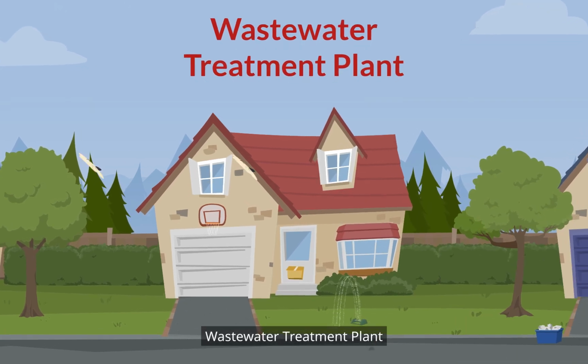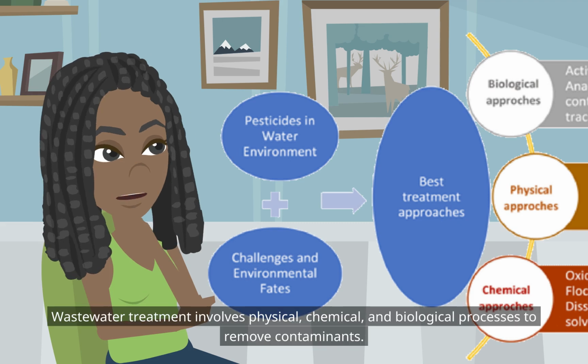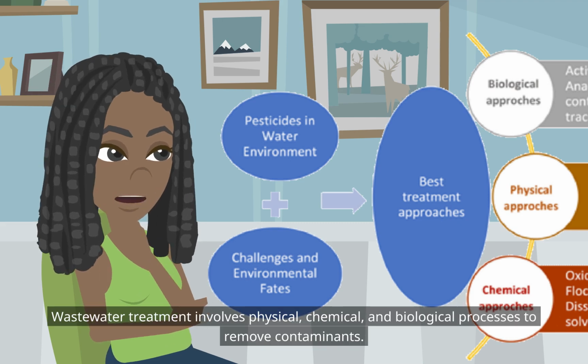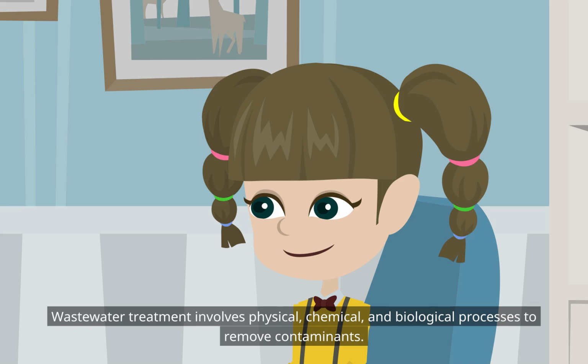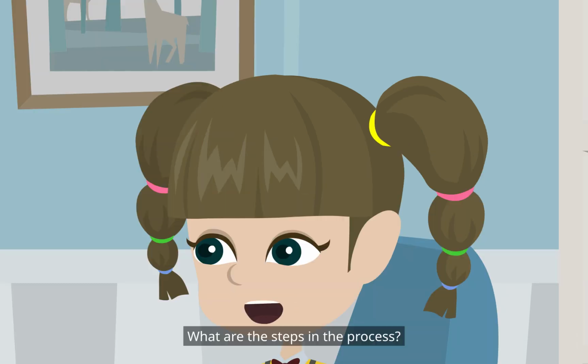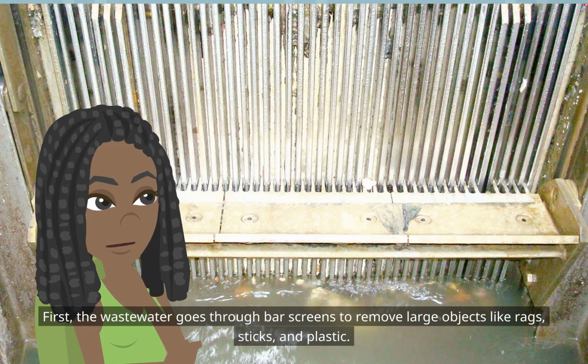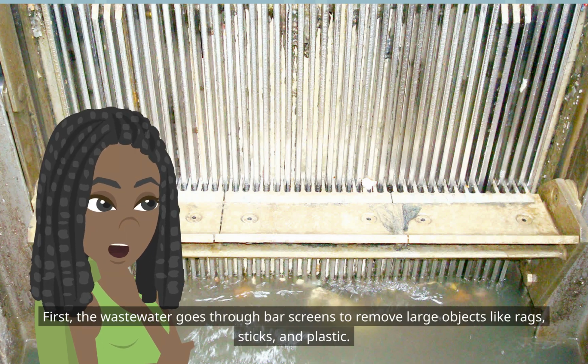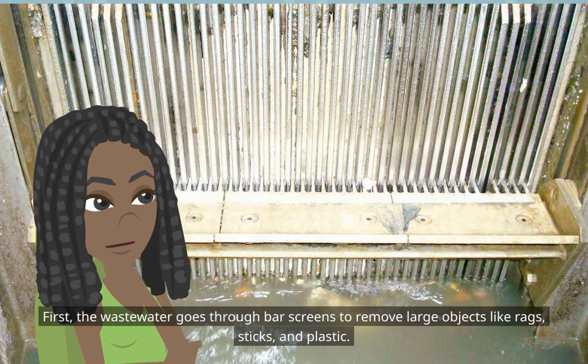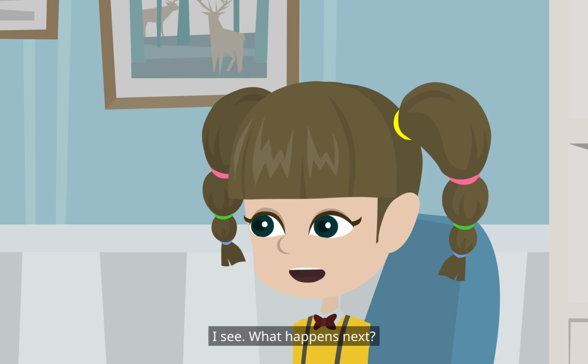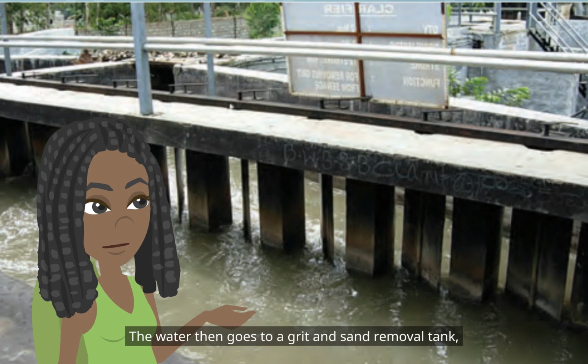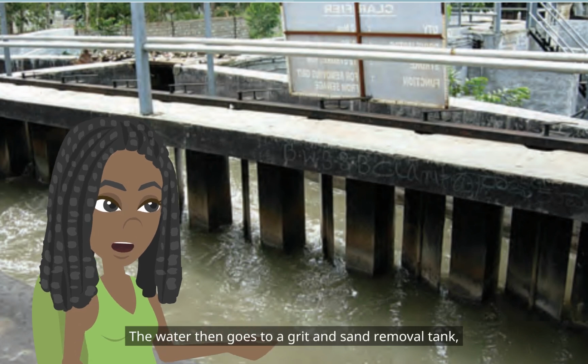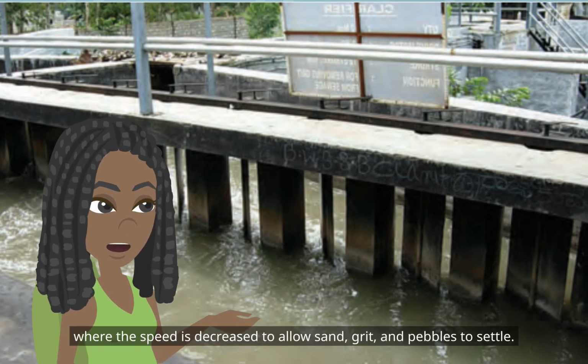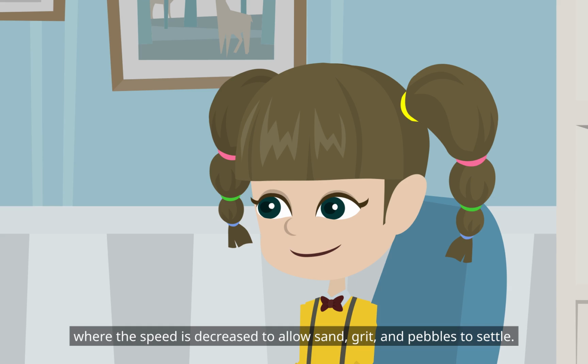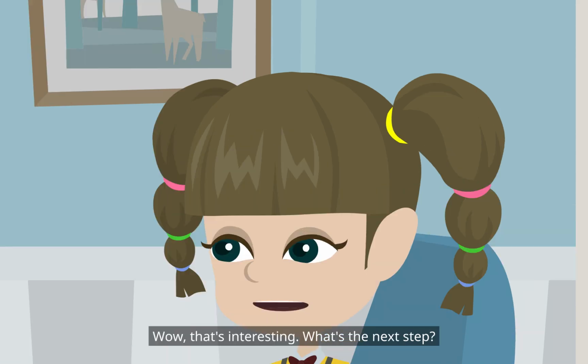Wastewater treatment plant. Wastewater treatment involves physical, chemical, and biological processes to remove contaminants. What are the steps in the process? First, the wastewater goes through bar screens to remove large objects like rags, sticks, and plastic. I see. What happens next? The water then goes to a grit and sand removal tank, where the speed is decreased to allow sand, grit, and pebbles to settle. Wow, that's interesting.